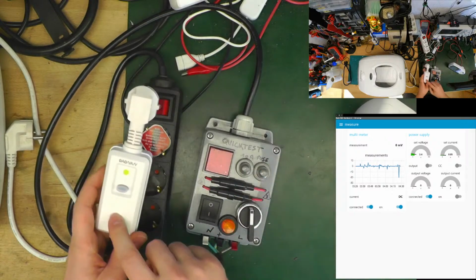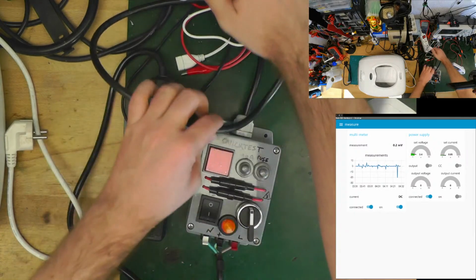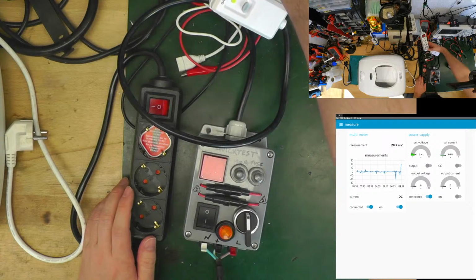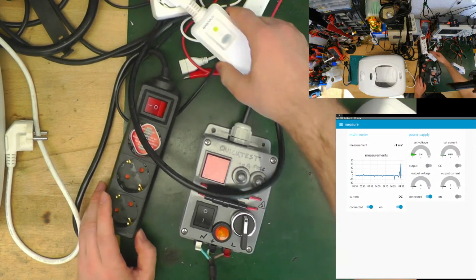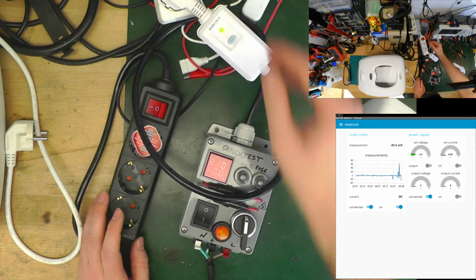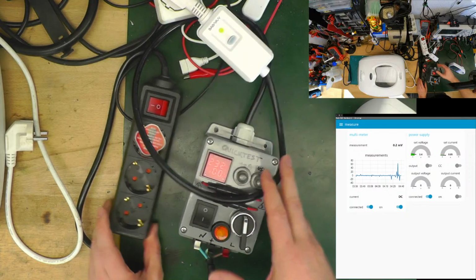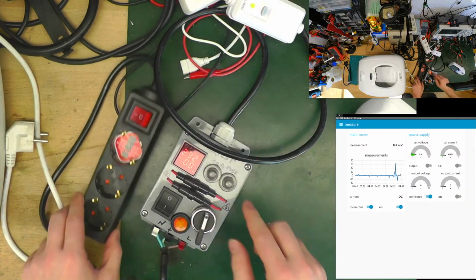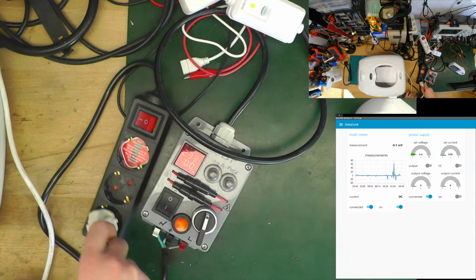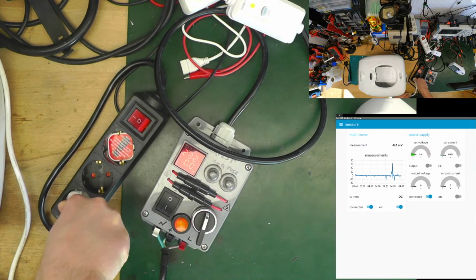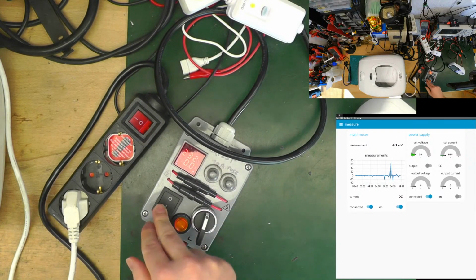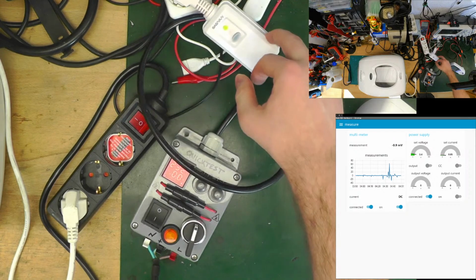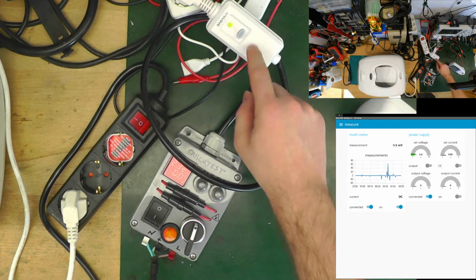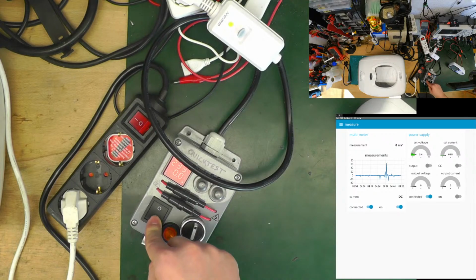Let's see if this trips before the mains trip. The mains thing trips, so here we have power. And here we see we have incoming power, no energy usage. If I plug this here and switch it on, we should see this switch off if we are fine, because this should trip earlier - or at least this is what I hope. So let's try.